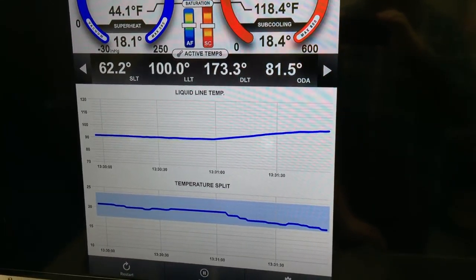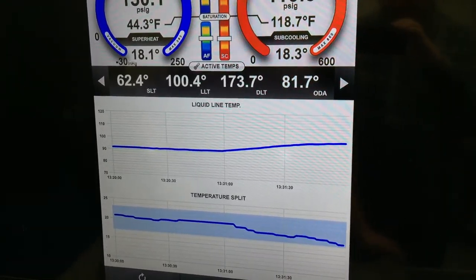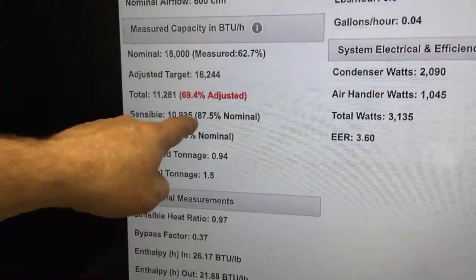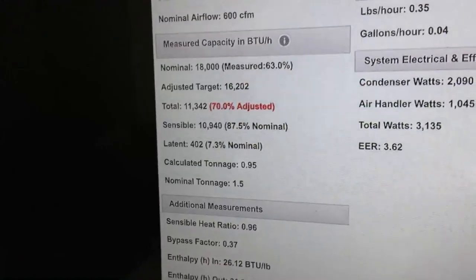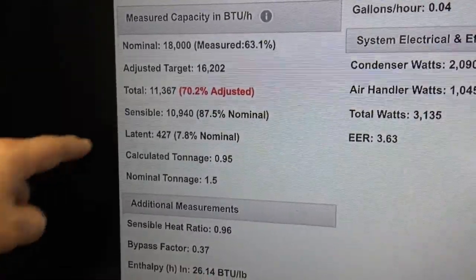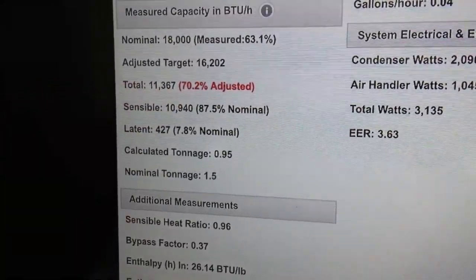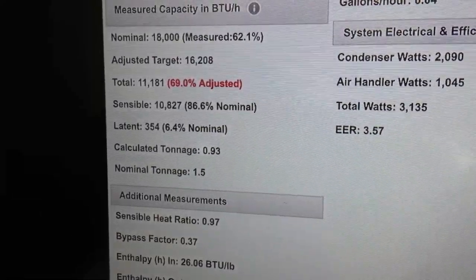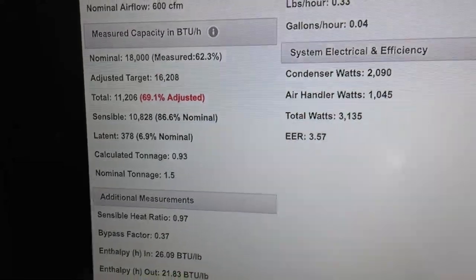All right, so it's continuing to drop down still. Our liquid line temperature is up to about 100 degrees, and let's see how this is impacting performance. I'm going to go back into the performance section for just a minute here. You can see what was 100% is now down to about 87% of our nominal capacity. Our latent has dropped down a tiny bit, or about stayed the same, and our total capacity has dropped down about 18%. And we're continuing to still drop off in sensible capacity on that system, and that's because that heat simply cannot be rejected.